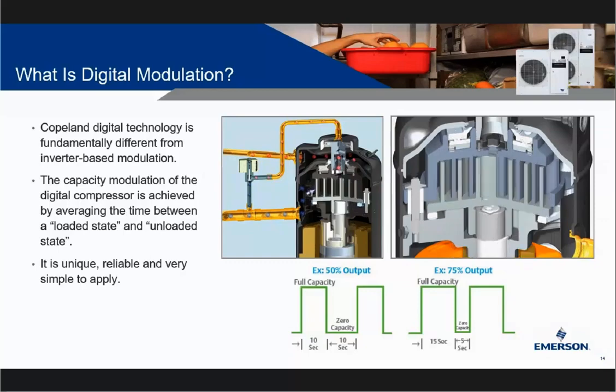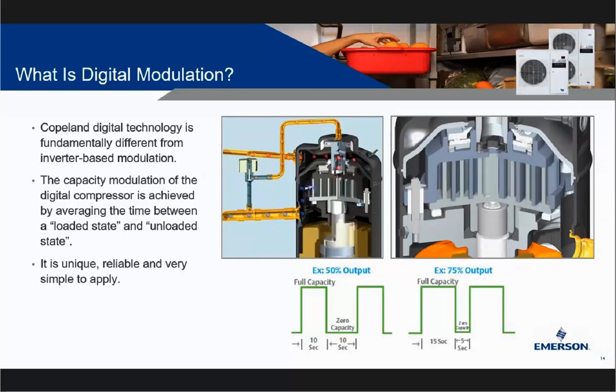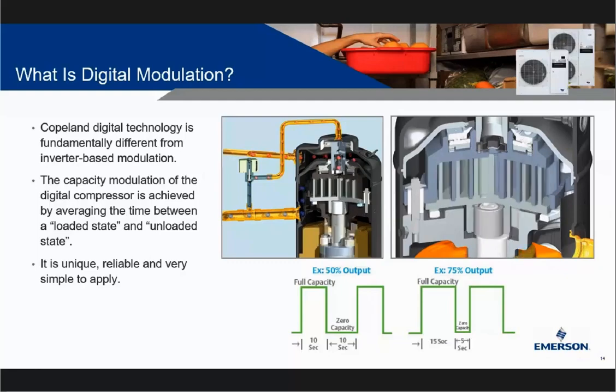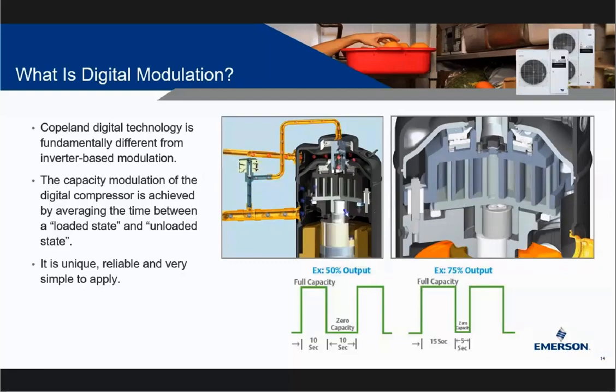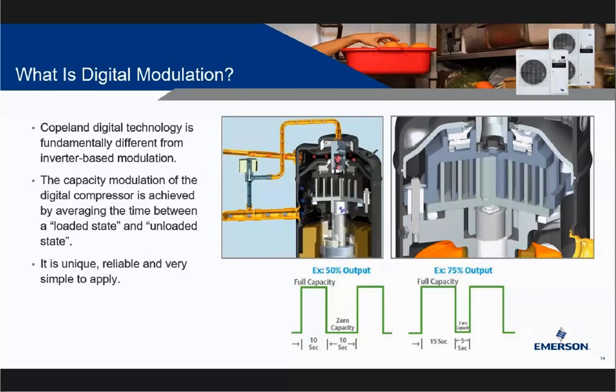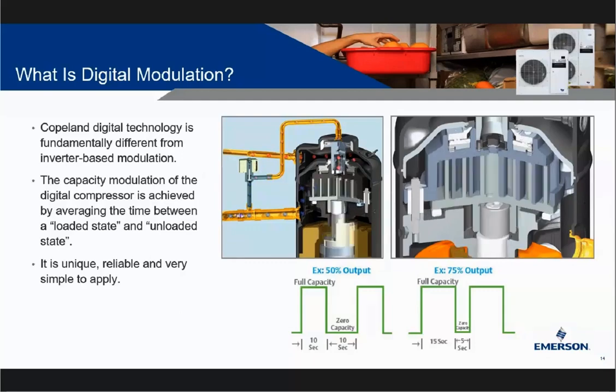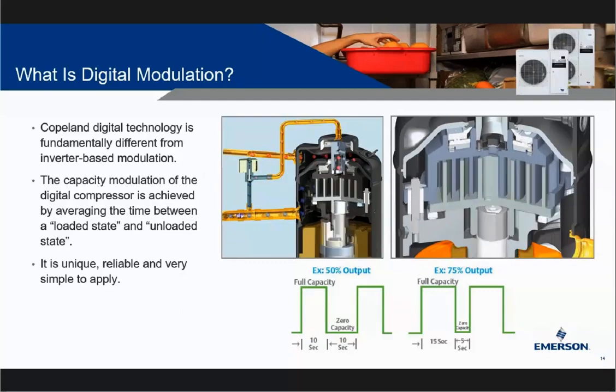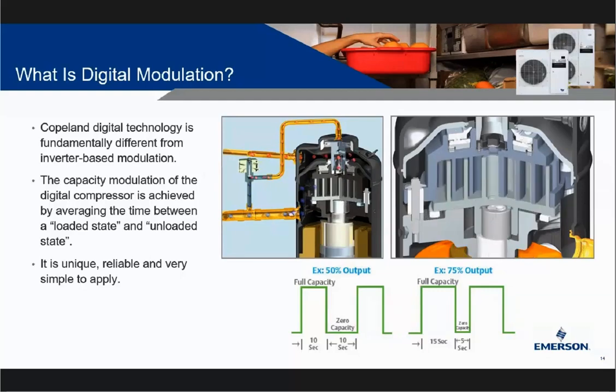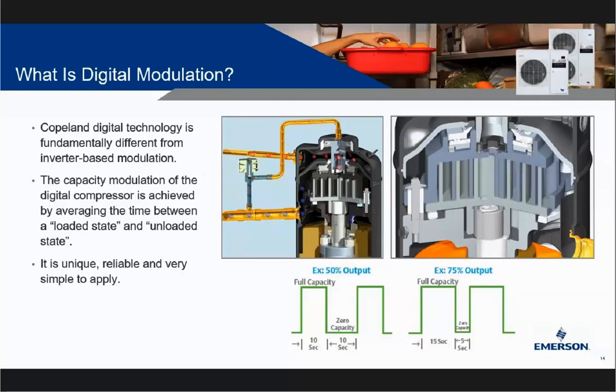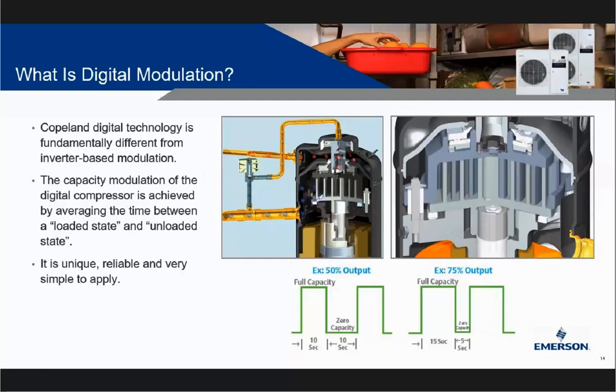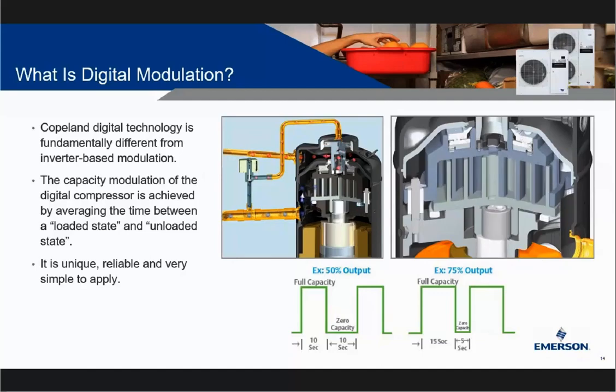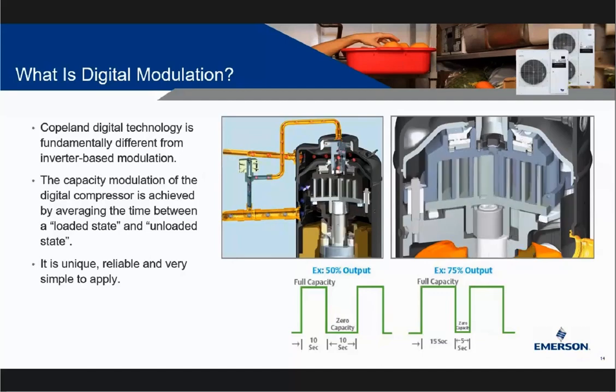So when its solenoid valve opens, the pressure decreases on the piston at the top of the scroll, and that allows the scroll to move axially by just 1 millimeter, but that allows compression to stop, without ever stopping the scroll. It will then alternate between these loading and unloading segments, and that will fulfill the need of the refrigeration load that it's connected to. To give you a few examples, I have down here at the bottom: if it needs 50% capacity at any given time, it's going to fully load for 10 seconds and unload for 10 seconds. So the controller looks at this in 20-second increments, and that's how it adjusts the modulation. Every 20 seconds, it's reevaluating the system and then modifying as needed.